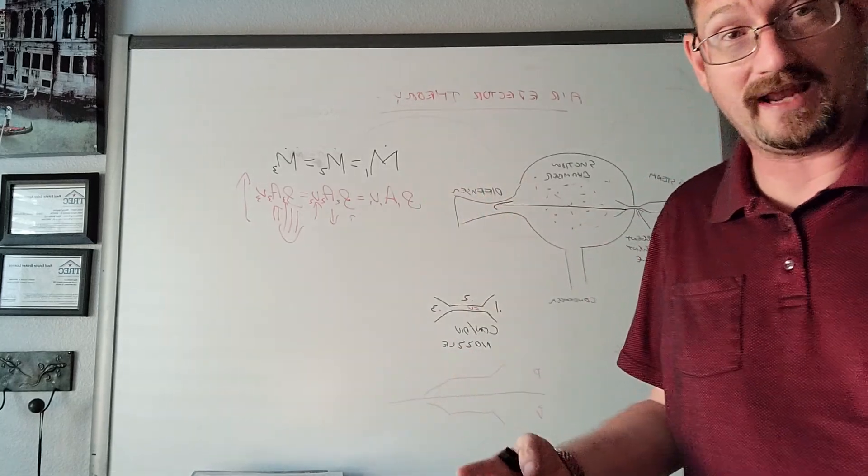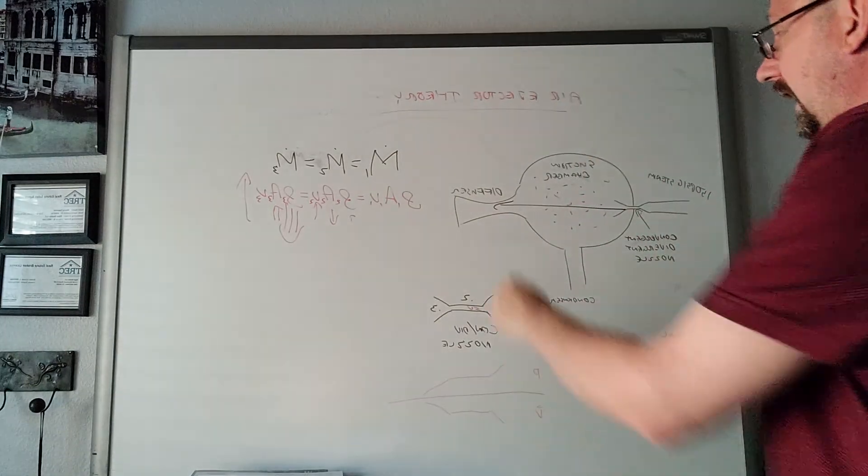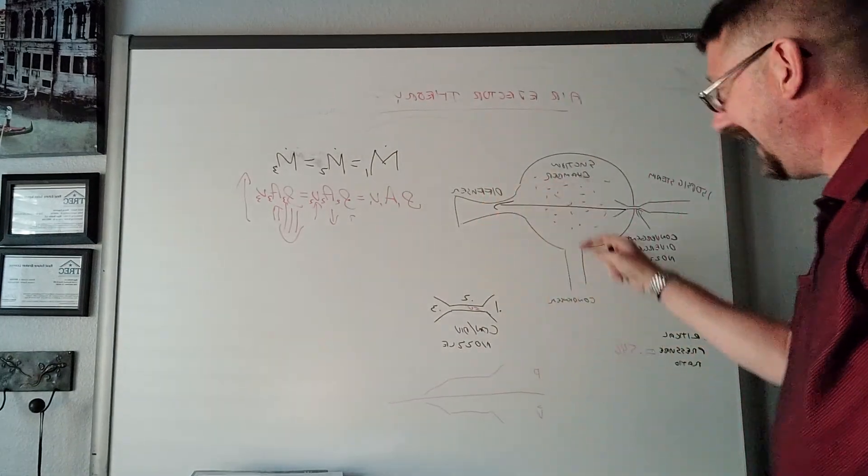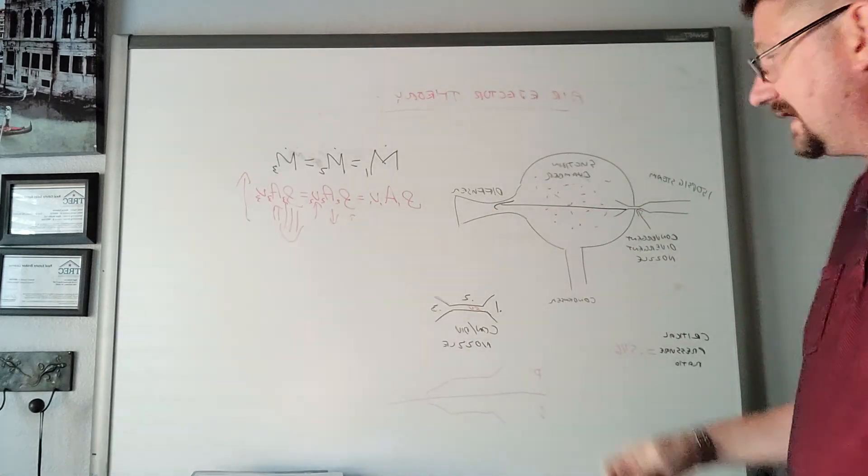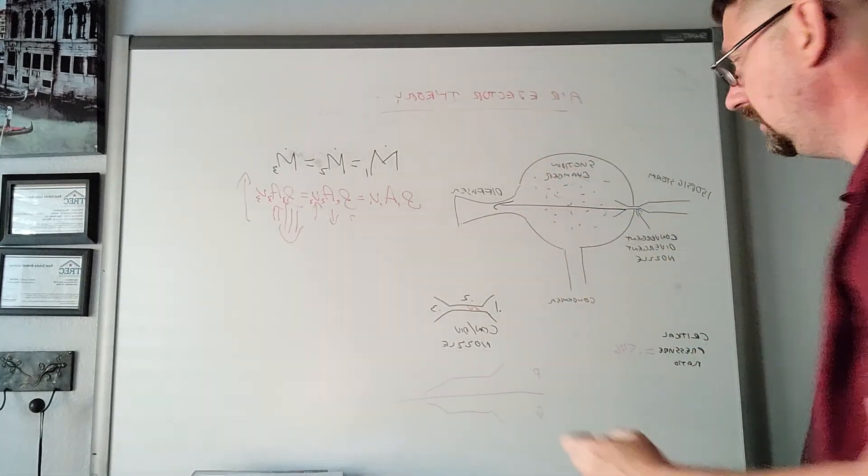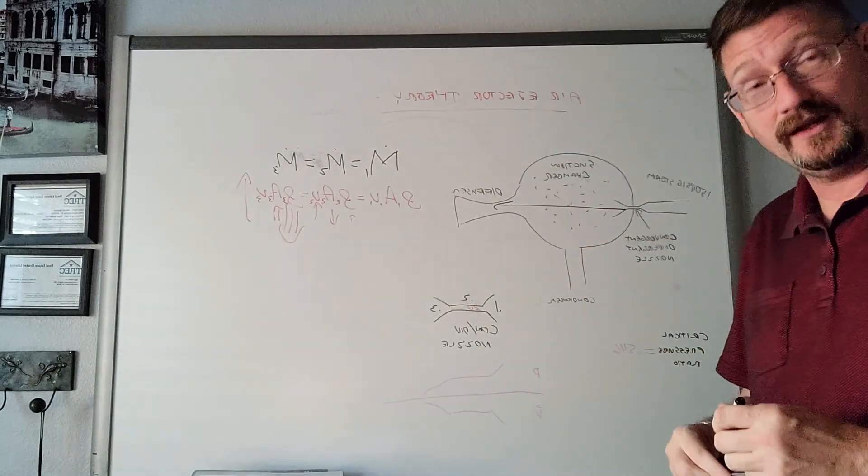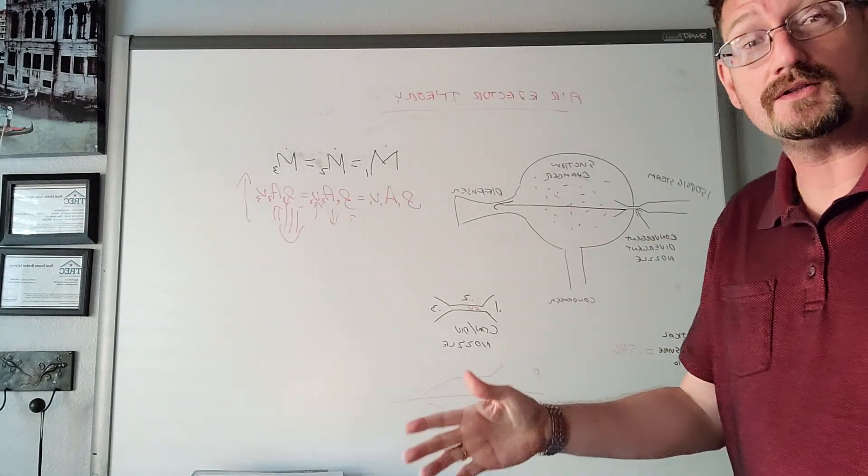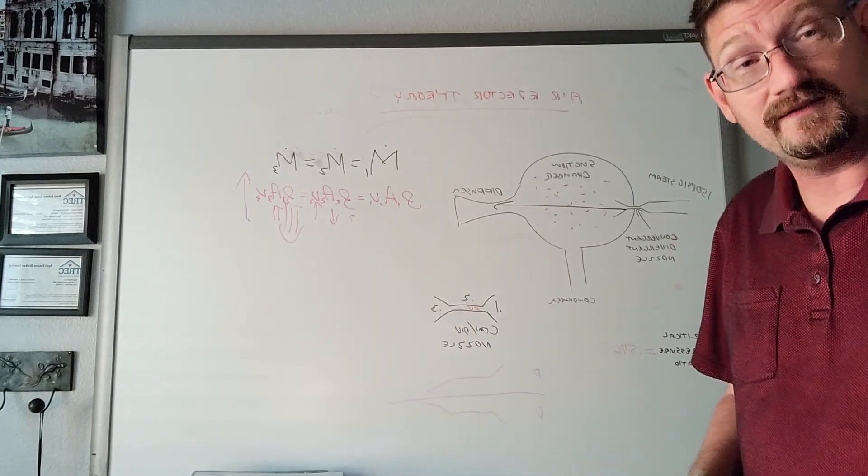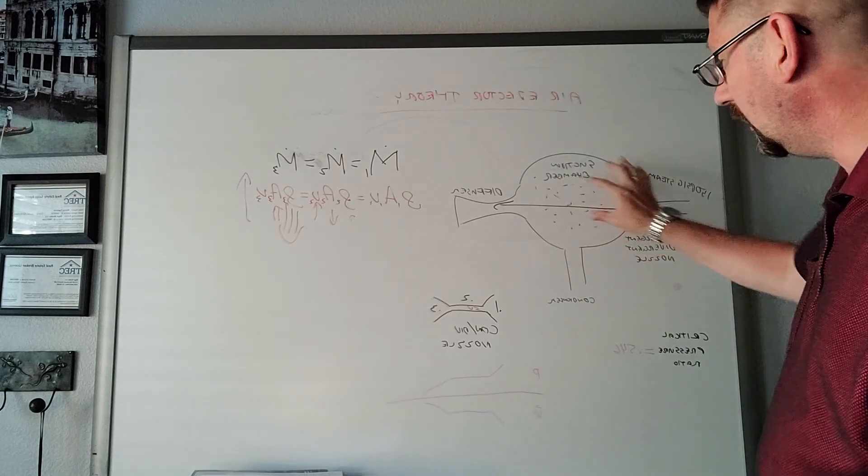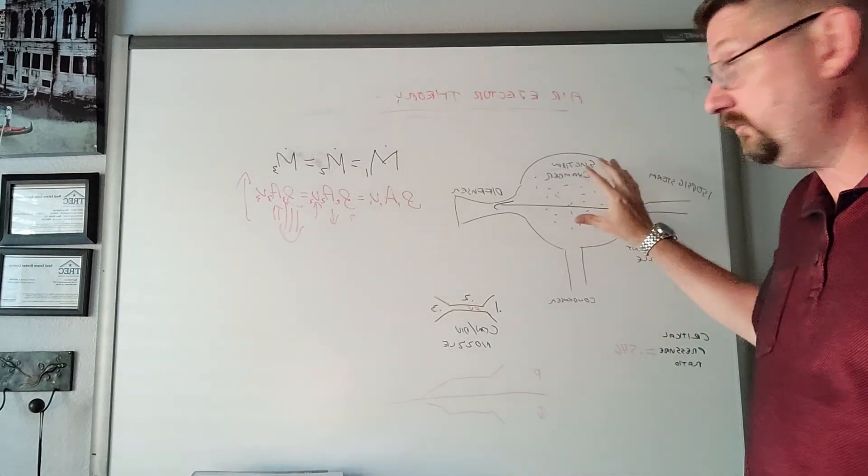As I knock these molecules of air and non-condensable gases out of the suction chamber, the air and non-condensable gases in the condenser are also a gas and will want to fill and occupy all portions of their container. I create a low-pressure area because I removed matter from the suction chamber, and matter from the condenser wants to flow up.